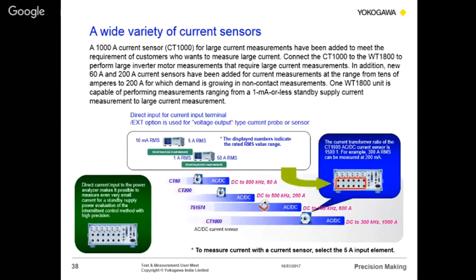CT60, CT200, CT1000 are 60 amps, 200 amps and 1000 amps respectively. You can measure up to 1000 amps, both AC and DC, with bandwidths like 500 kilohertz, 800 kilohertz or 300 kilohertz. And it's not only that, any other manufacturer's CT can also be configured. Some of the applications, now we more or less have an idea of what kind of equipment we have. Can a current sensor be plugged into this power scope? Current sensor? Yeah, you can.